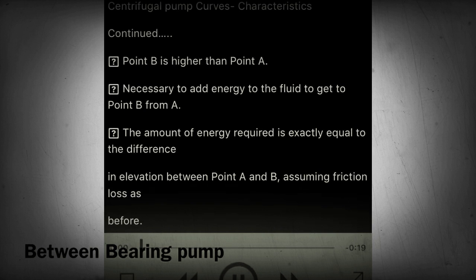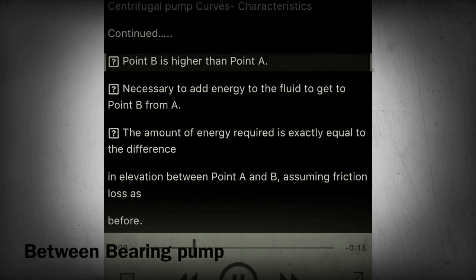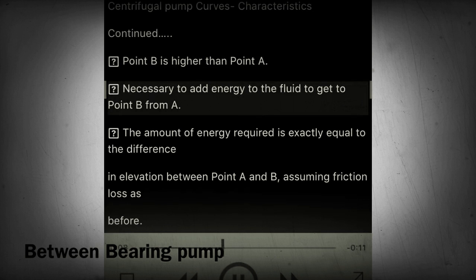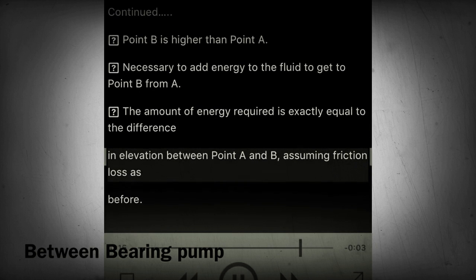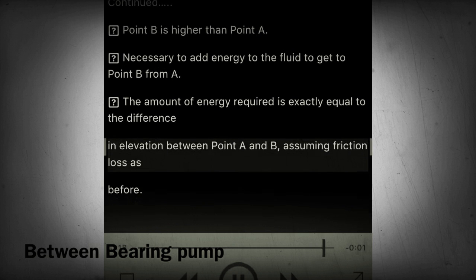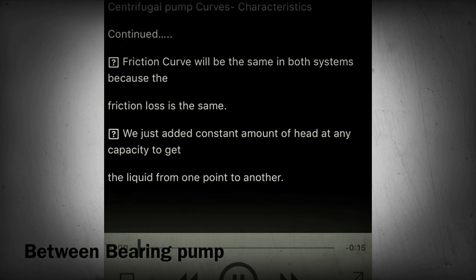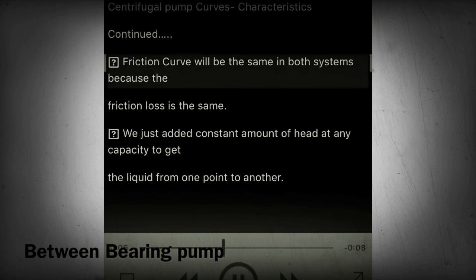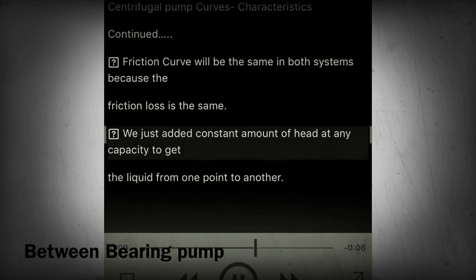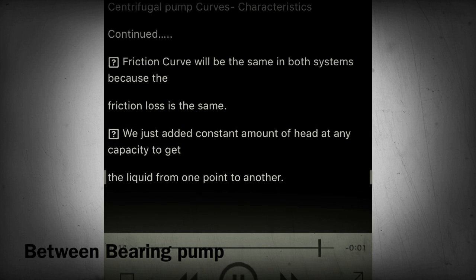Section 31-32 - When point B is higher than point A, it is necessary to add energy to the fluid to get from point A to point B. The amount of energy required is exactly equal to the difference in elevation between points A and B. Assuming friction loss as before, the friction curve will be the same in both systems because the friction loss is the same. We just added a constant amount of head at any capacity to get the liquid from one point to another.